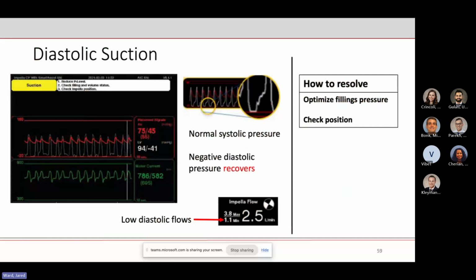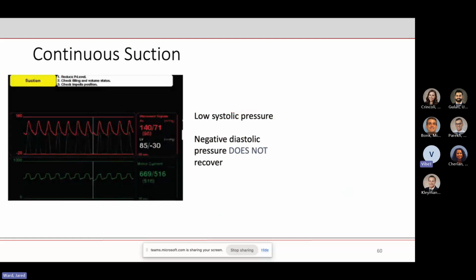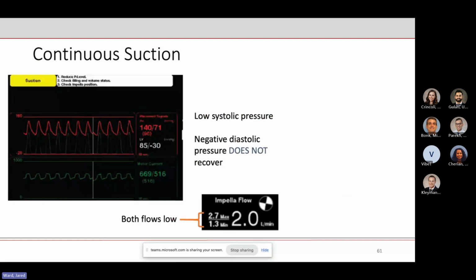This is almost always a volume issue, whereas with continuous suction events, right? The diastolic pressure doesn't recover. You don't get that nice overlap of the aortic pressure and the LV pressure. Aortic pressure remains above the LV pressure, right? And in this case, both your systolic and diastolic flows will be lower because the Impella is constantly suctioning. It wasn't able to recover from it.